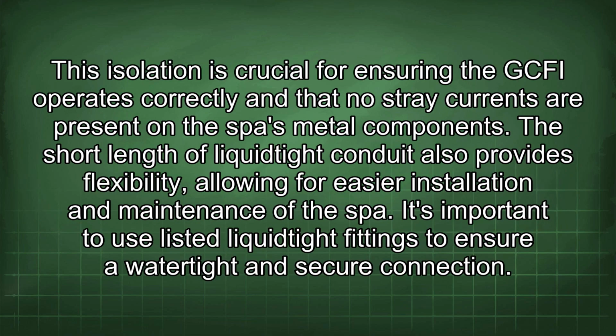This isolation is crucial for ensuring the GFCI operates correctly and that no stray currents are present on the spa's metal components. The short length of liquid-tight conduit also provides flexibility, allowing for easier installation and maintenance of the spa. It's important to use listed liquid-tight fittings to ensure a watertight and secure connection.